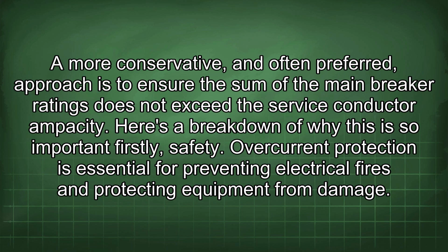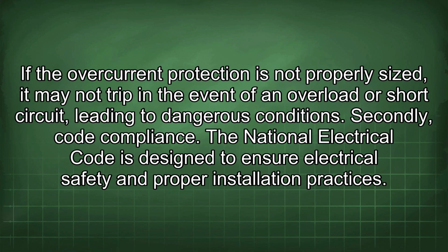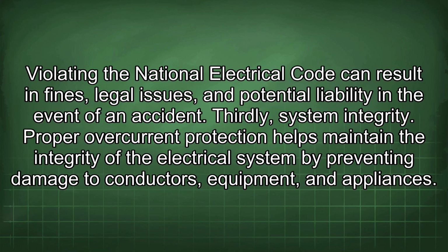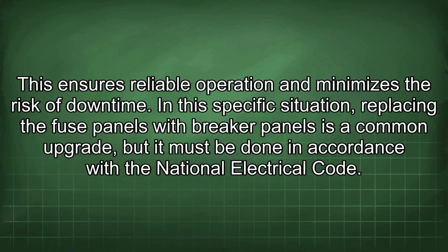Firstly, safety. Overcurrent protection is essential for preventing electrical fires and protecting equipment from damage. If the overcurrent protection is not properly sized, it may not trip in the event of an overload or short circuit, leading to dangerous conditions. Secondly, code compliance. The National Electrical Code is designed to ensure electrical safety and proper installation practices. Violating the National Electrical Code can result in fines, legal issues, and potential liability in the event of an accident. Thirdly, system integrity. Proper overcurrent protection helps maintain the integrity of the electrical system by preventing damage to conductors, equipment, and appliances. This ensures reliable operation and minimizes the risk of downtime.